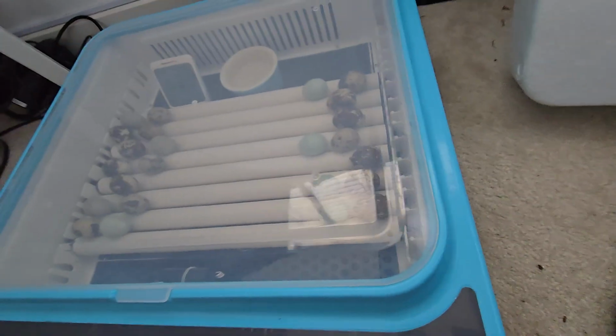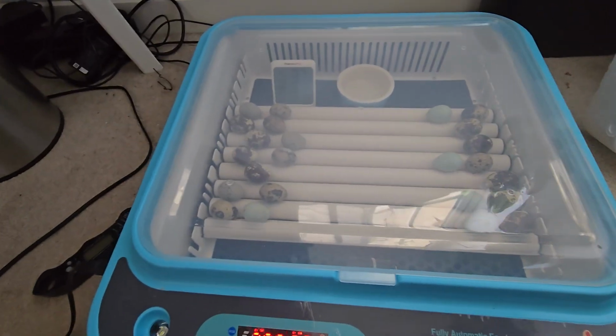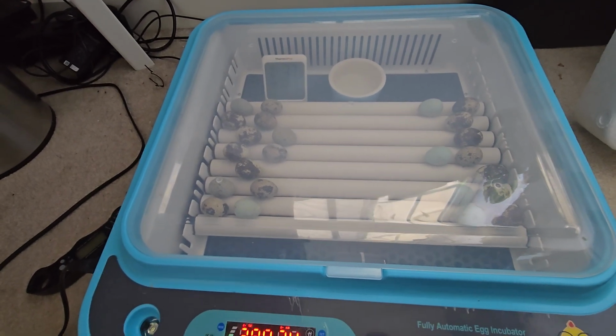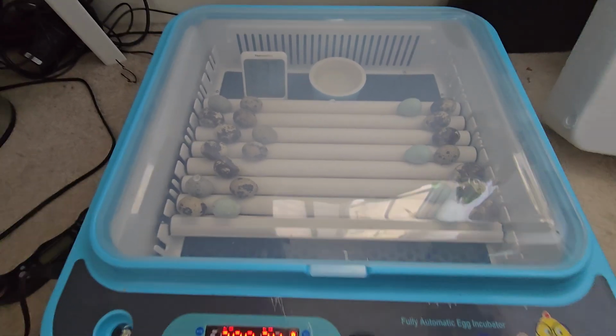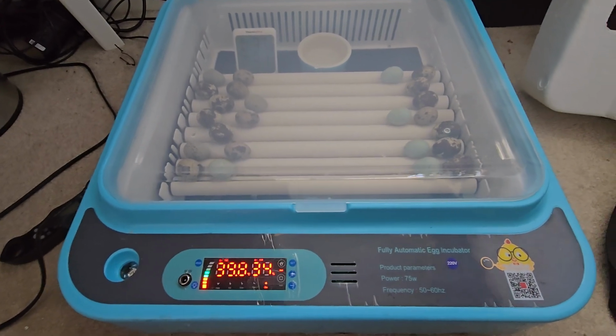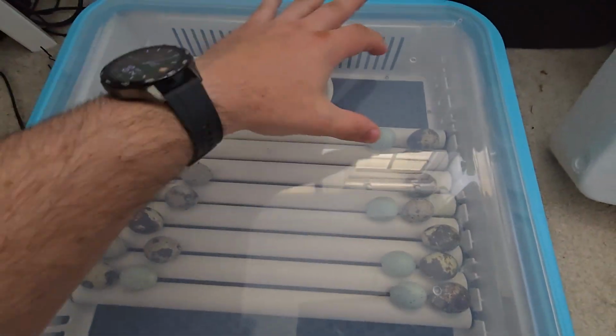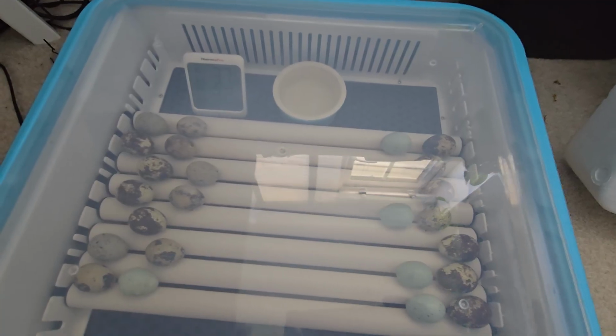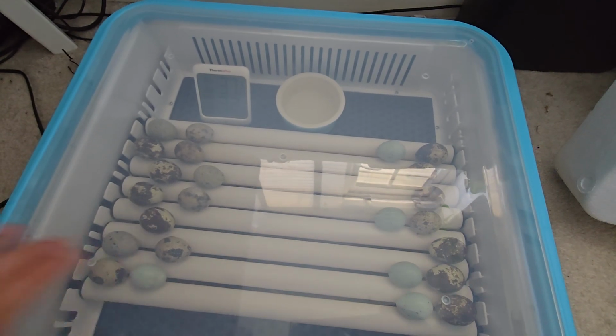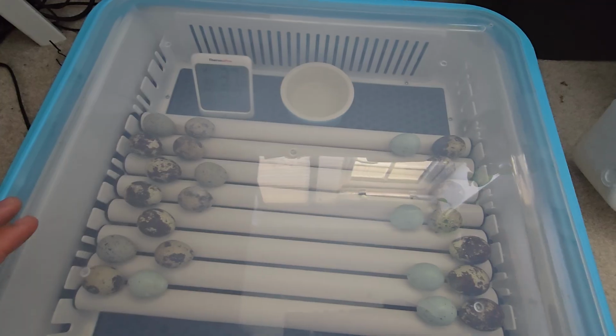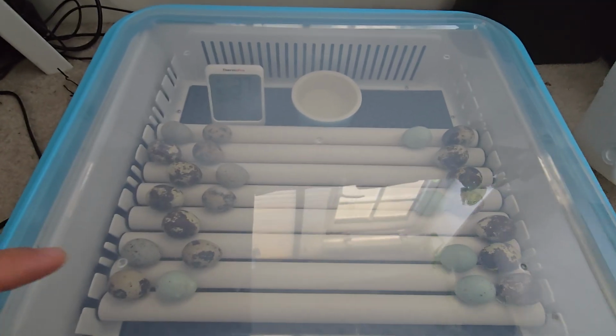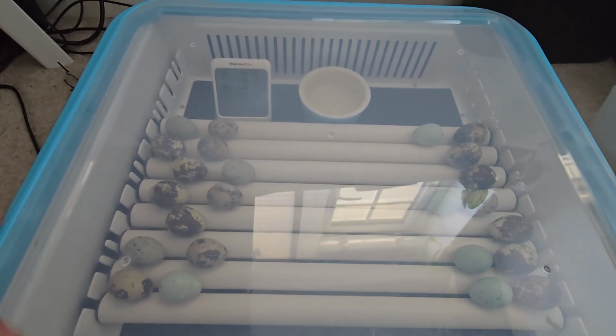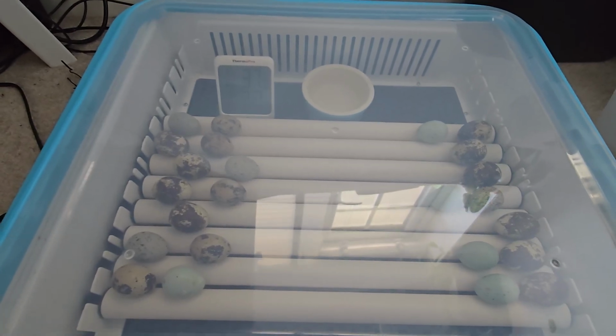When controlling the humidity, this incubator comes with these ports here, as well as pipes, which you can put a normal drink bottle on top of, which will basically feed it water 24/7, as much as you need. The problem is those channels run three channels like this across the whole incubator, and they tend to push the humidity far too high because it's the whole length of the incubator. For me, I need to keep this at 50% humidity, or in that range.